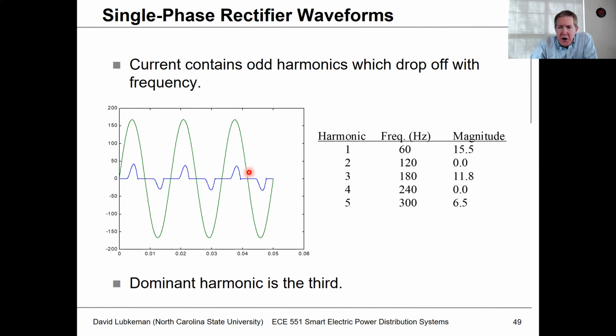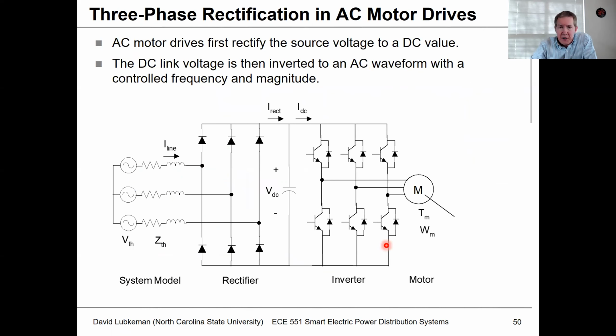In this particular waveform right here, you see the fundamental is at 15.5, the third harmonic would be kind of significant, 11.8 amps, and the fifth harmonic would be 6.5. So the dominant harmonic in this case would be the third harmonic.